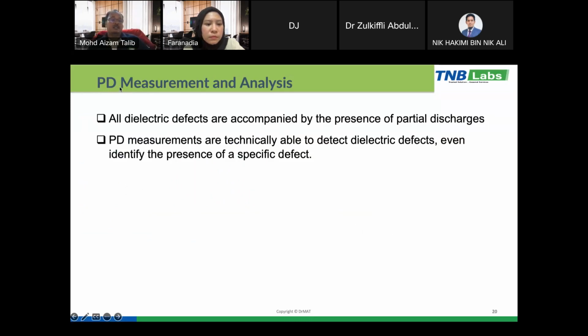So the next slide is on the PD measurement and analysis. We know that all defects in the material will be accompanied by the presence of partial discharge. It means that when we have a fault in the insulation, it will create a partial discharge. So through the measurement of the discharge, technically we are able to detect the defects, and we can even identify the type of the defect based on specific patterns.